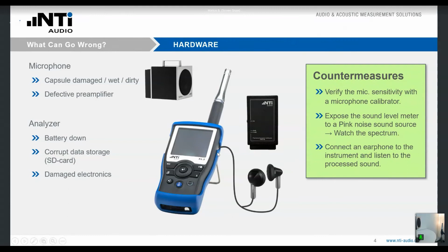And the third approach would be to connect an earphone to the audio output of our test instrument. And by that, you can listen to the processed sound signal. So the incoming sound signal, the sound waves, which are translated into electrical signal, are made audible in this way. And if anything goes wrong on the signal path, maybe it's some distortions or whatever, you would hear that rather quickly with your earphone. So this is another way how you can detect potential problems in your test and measurement system.